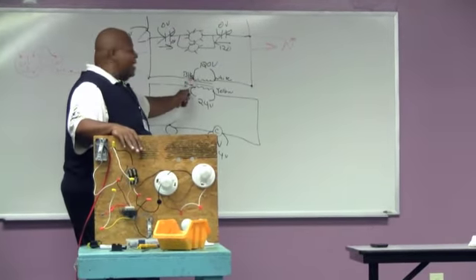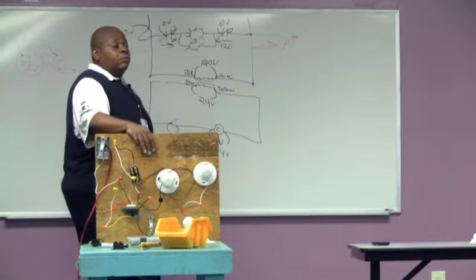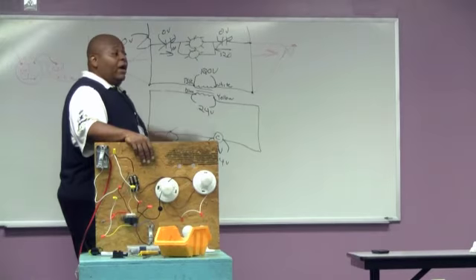I'm going to drop down to the transformer, black and white. Put your leads there, you should get 120 volts. If you don't have 120, you're not going to have 24.